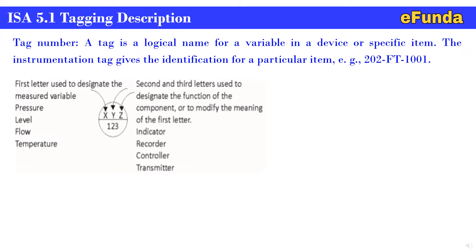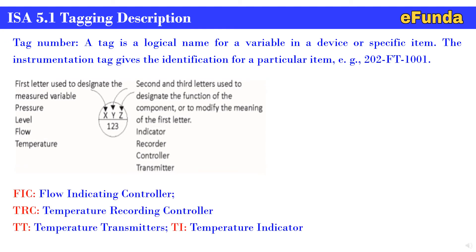Y is the second and third letter used to designate the function of the component or to modify the meaning of the first letter - that is indicator, recorder, controller, transmitter. For example, FIC is flow indicating controller, TRC is temperature recording controller, TT is temperature transmitter, TI is temperature indicator.